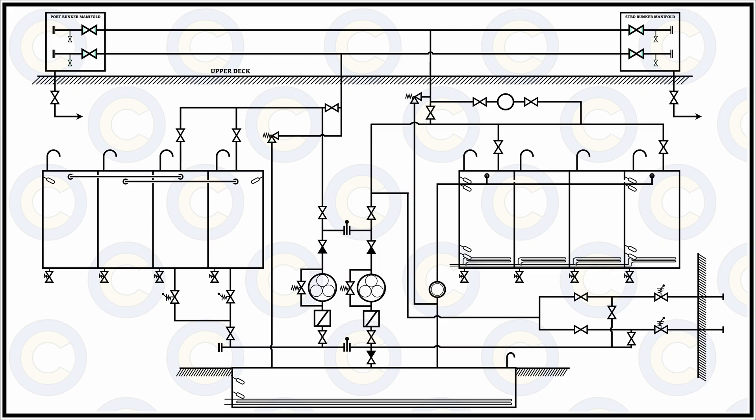On both sides you will be having standard flange connections to connect the hoses that are received from the shore or barge, and a valve after it immediately to isolate or segregate this particular connection. For example, if we are receiving bunker from the starboard connection then we can isolate the port opening by closing these valves and locking them and vice versa.